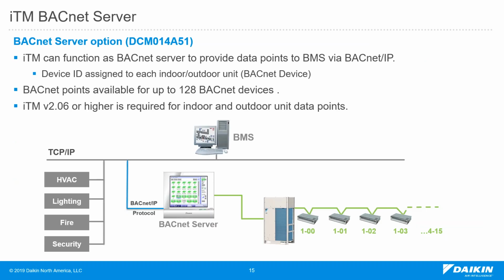If we're gonna talk about the server function, the server function is kind of the opposite of the client. Usually, if you have a job that requires server function, that means there's a BMS at that job site. With our server function, we can provide indoor unit data and outdoor unit data to the BMS. Indoor unit data can be monitored and controlled. Outdoor unit data is monitoring only, and we can provide data for each outdoor unit, main or sub outdoor unit. And that's up to 128 BACnet devices.